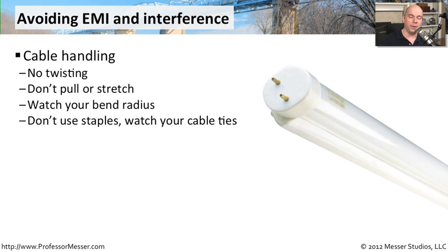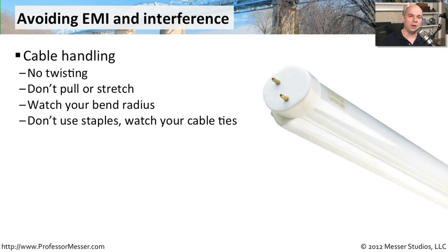There's also something called a bend radius — you don't want to make a 90-degree turn with the cable. Different types of cable allow different bend radius values, and the same applies to fiber. Check the manufacturer's requirements for the cable or fiber you're using to determine the correct angle of bend. Also make sure you don't use staples or cable ties — anything that could possibly kink or cause a problem with the copper or fiber inside that bundle of cables.